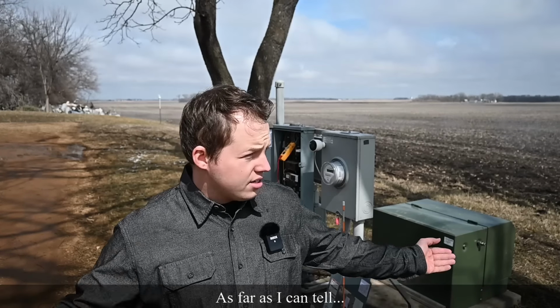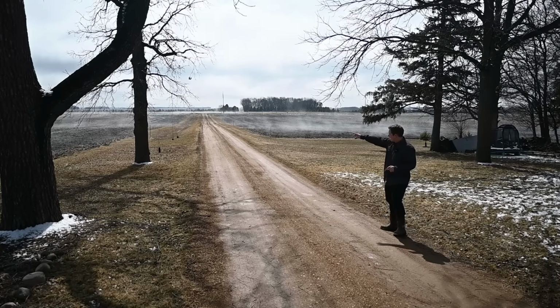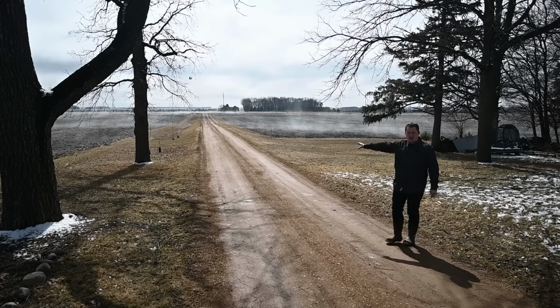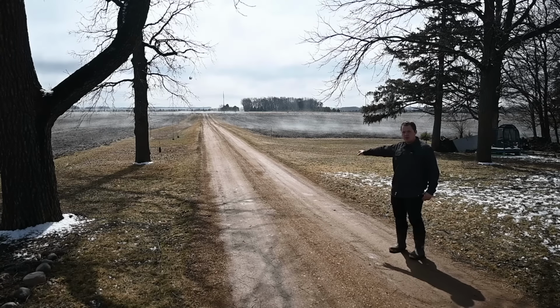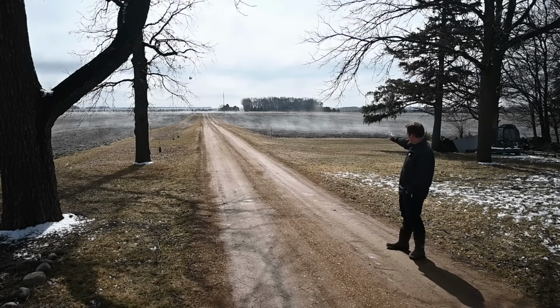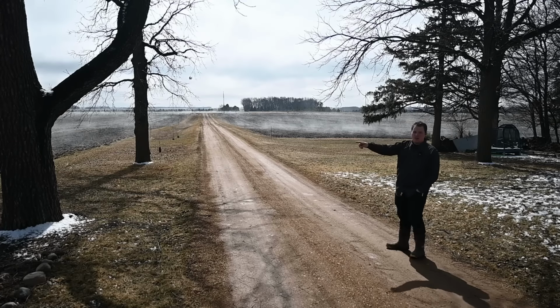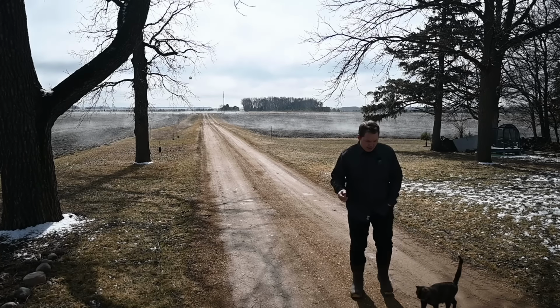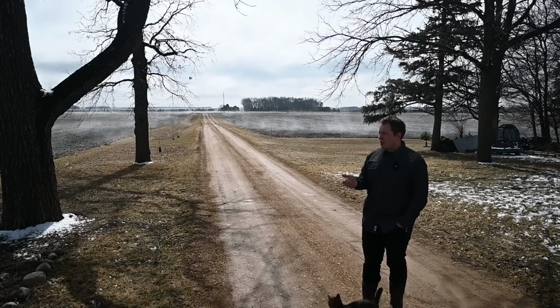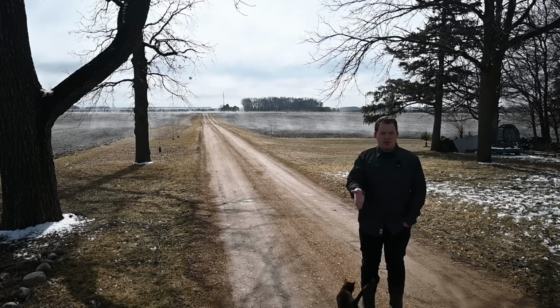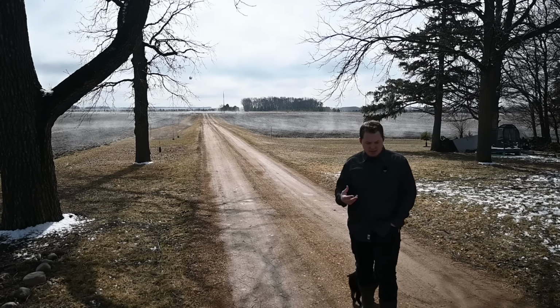But in this case, it is actually current that is flowing from that transformer and into the ground. So obviously there must be some way for that current to make it back to its source. So I don't know if that source could be those power lines way out there by the road. That's about 1,000 feet away, where the closest grounding electrode would be pounded in the ground. There's another transformer over there. The big power line going across there is actually a transmission line, and so I don't think that one's involved, but maybe that transmission line has some kind of a grounding conductor that is being used for some reason.